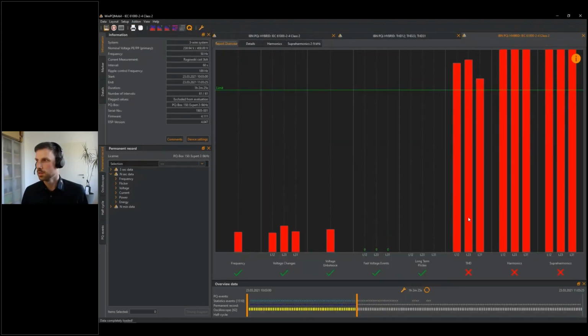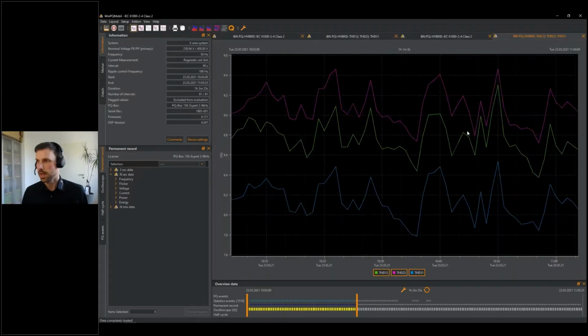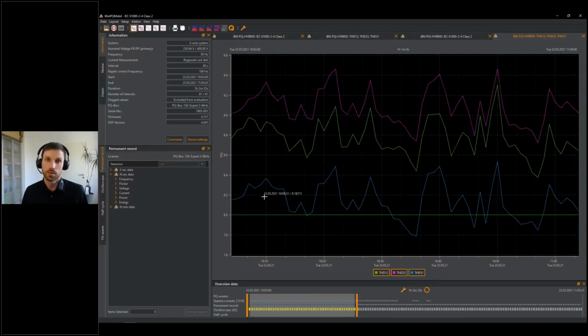So norm evaluation again. And I see, well, the harmonic levels are bad. I only see the high levels, about 9%. If I want to see the limit value, I can add the limit value as well with limit lines. Click on OK, and I see the limit value is 8%. So this is very typical for many standards.